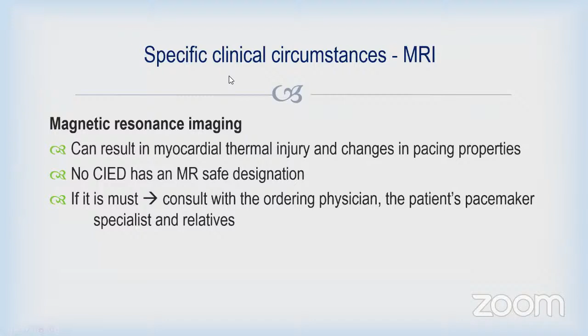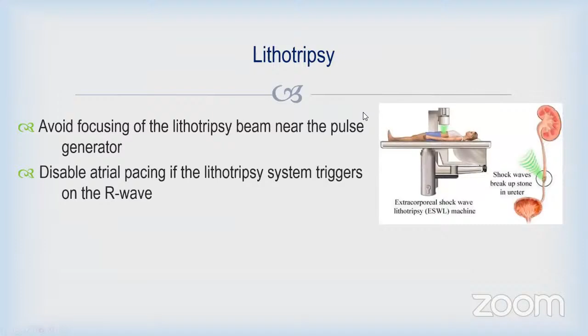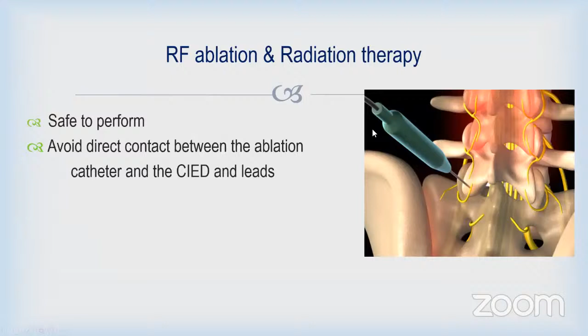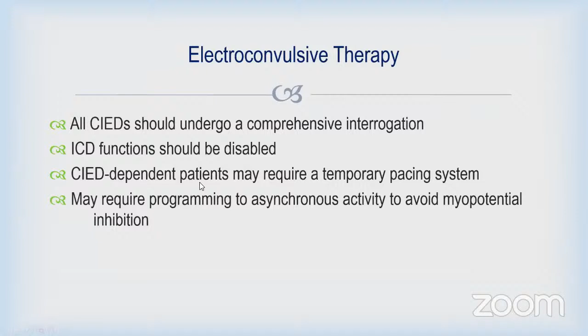Lithotripsy and RF ablation, radiation therapy: as long as the beam is away from the pacemaker, it can be safely done. If the beam is very near to the pacemaker, not in lithotripsy but in RF and radiation therapy, then probably you need to put the patient on asynchronous mode. ECT: again, a lot of studies and case reports say that ECT will not affect, and even if it affects, it will be transient. So ECT plus scoline can be safely done.